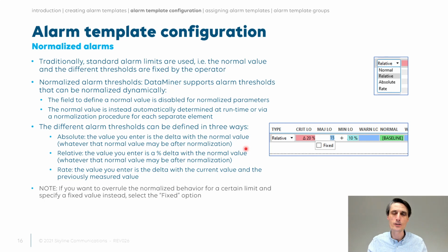Let's just assume, for instance, the total processor load. If I want to configure a normal value and what is a high value, well, one server could maybe be such that I want an alarm if it's above 50%, while the other one is maybe all the time at 50%, and I only want to generate an alarm when it's above 80%. So how can I do that? Well, you can, of course, duplicate your alarm templates. You can have an alarm template with high thresholds and one with lower thresholds. So that's a valid approach.